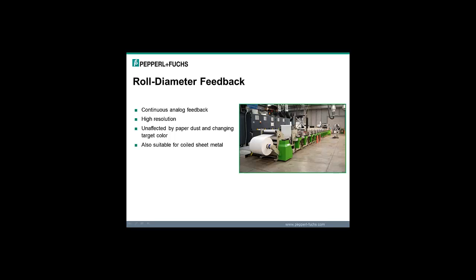Another popular ultrasonic application, whether it's rolls of paper or rolls of sheet metal, is to get roll diameter feedback, so you know when you're getting to the end of your roll. Again, continuous analog feedback is preferred, and the nice thing with the ultrasonic sensors is they aren't affected by paper dust, they aren't affected by changing target color. I mentioned they're good for sheet metal, and in the previous application we said they're good for oils and dirt and dust and contaminants, all that stuff. So they're a great product for roll diameter feedback.